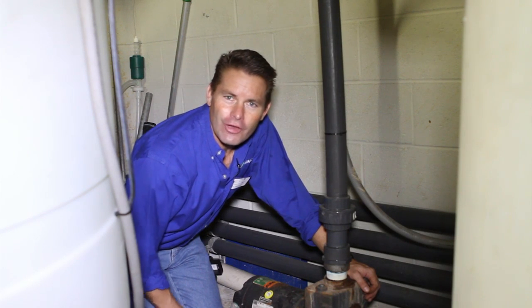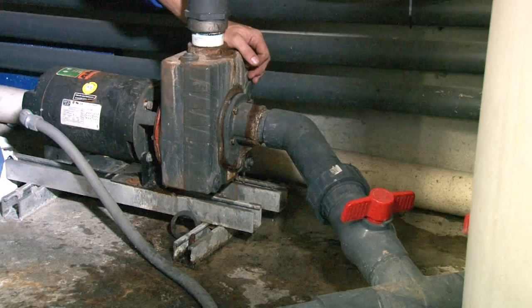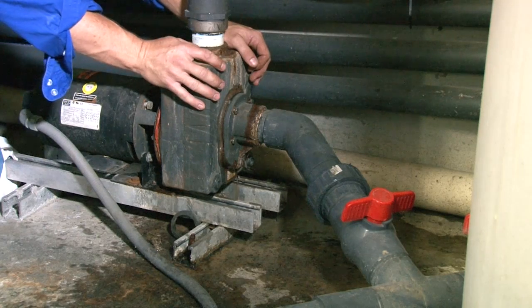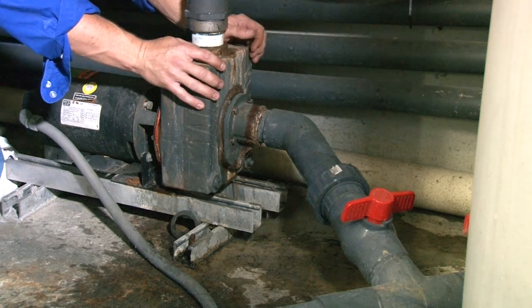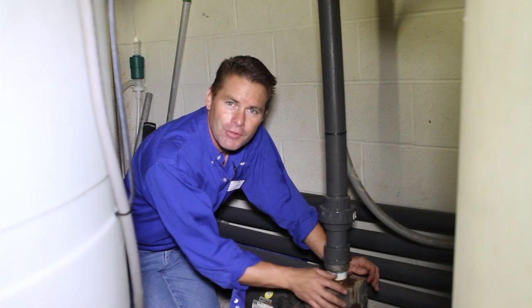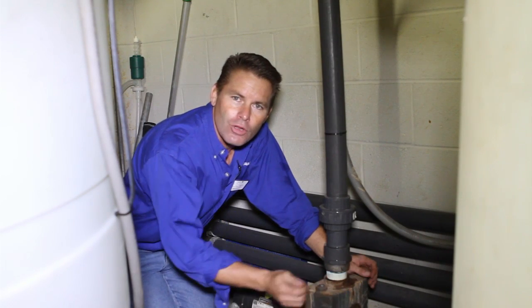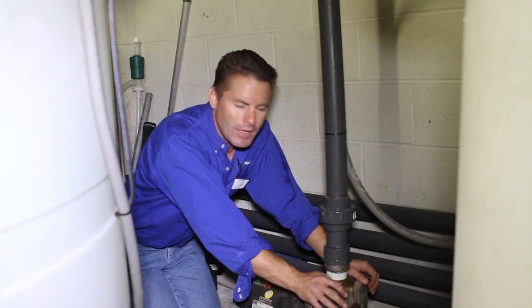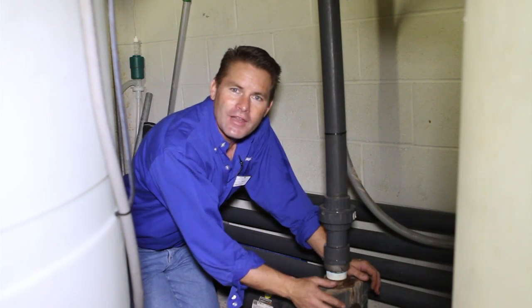This video is going to show you how to take a clog out of your pit pump. These pit pumps will handle large solids up to basically ping pong size solids and pump it through. But things like rags or long cord things tend to clog up the impeller. So you may get a clog and you've got to clean it out.